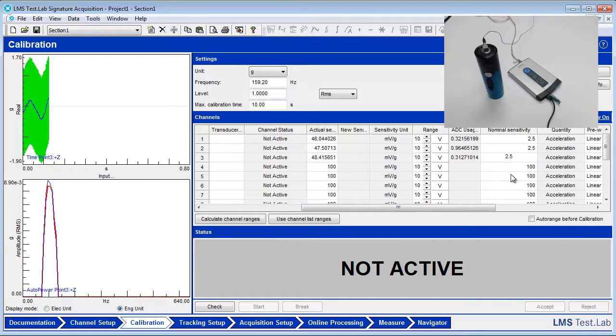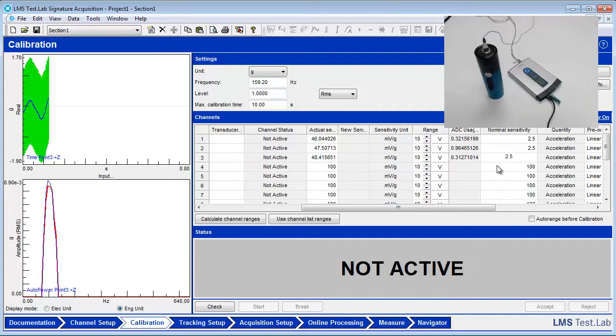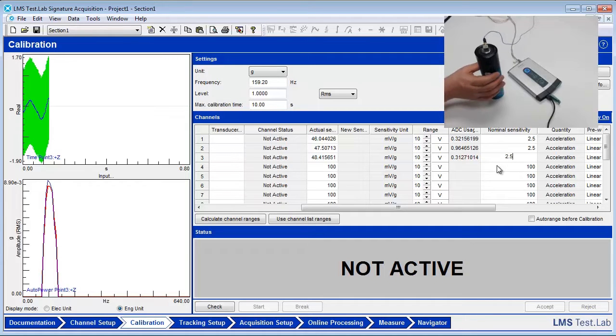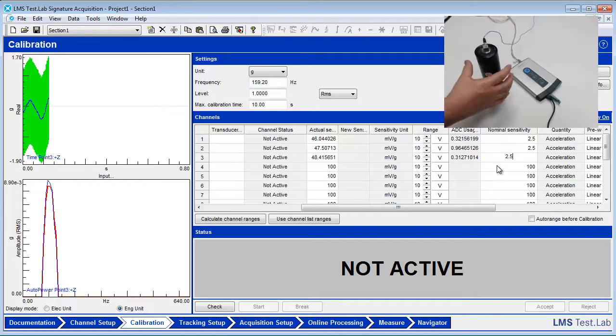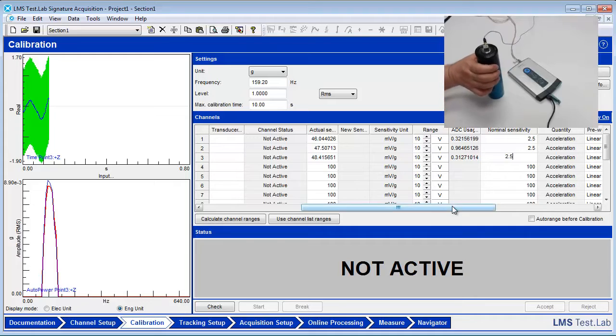Attach the accelerometer itself to the top of the calibrator using beeswax. The direction that is facing up is the direction that will be calibrated. In this case, this is the Z direction. Turn on the calibrator. It is good practice not to attach the accelerometer while the calibrator is running.